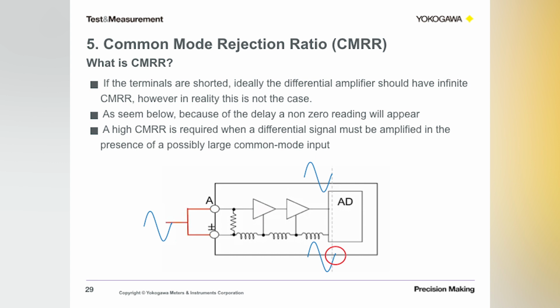In general, since it's the same input, the CMRR will contribute to the amplitude uncertainty rather than the phase shift uncertainty. So your measuring device should have the capability of rejecting the influences of common mode voltage. Some DAQ devices have it, others don't, but for power measuring devices, it is a key factor. So be sure to evaluate this specification well before you decide on choosing an instrument.